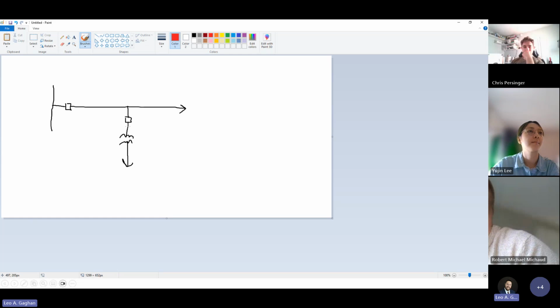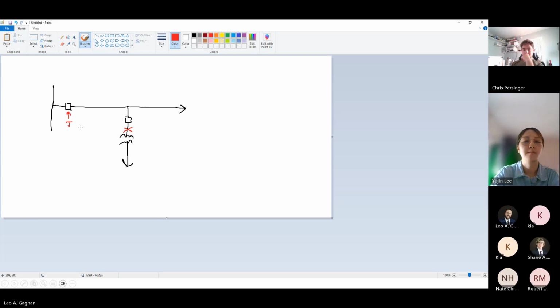So the example in question here would be, if a fault were to happen right here, and our instantaneous element were to be set sensitive enough to see that. Well, this breaker would trip. This breaker would trip. If this breaker does not have reclosing, it'll stay open. But this one does have reclosing. It will reclose, and then everyone will be happy because the line gets restored. So sometimes that'll be acceptable. Sometimes they don't want to take those risks, those potentials for outages, and they'll just have the instantaneous element come up just short would be the plan.